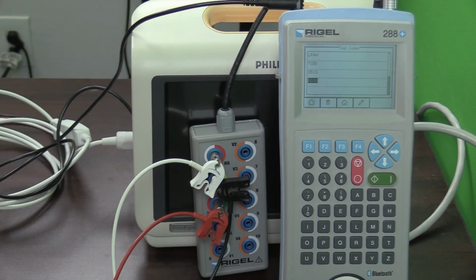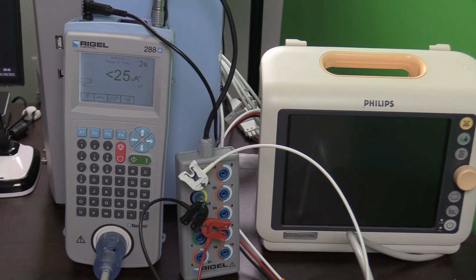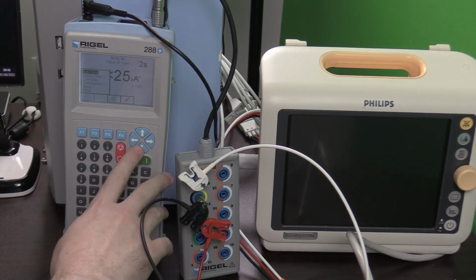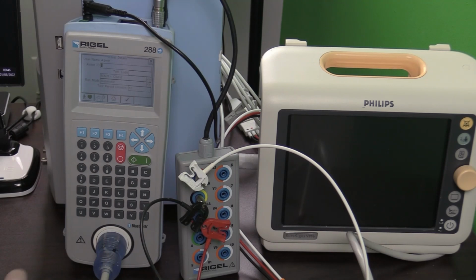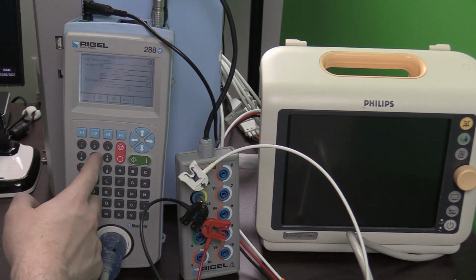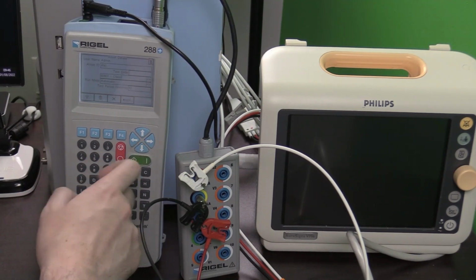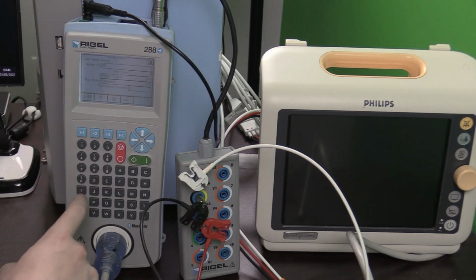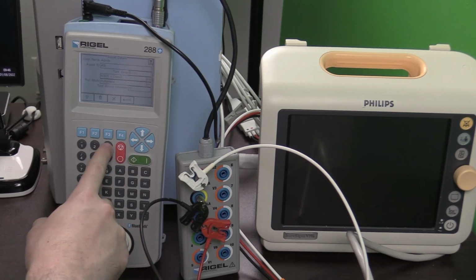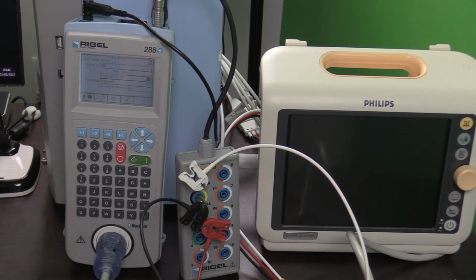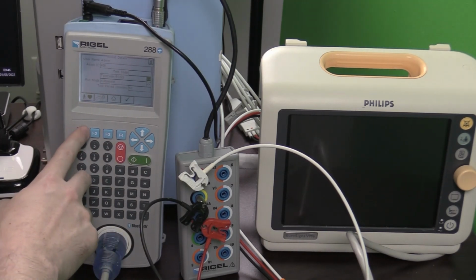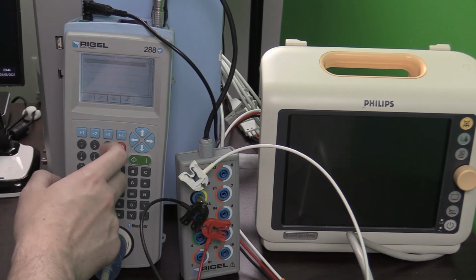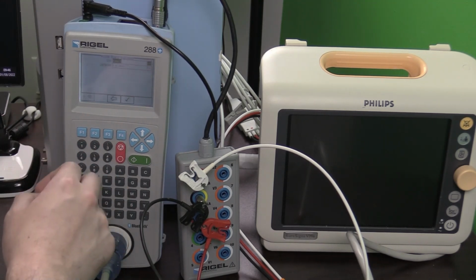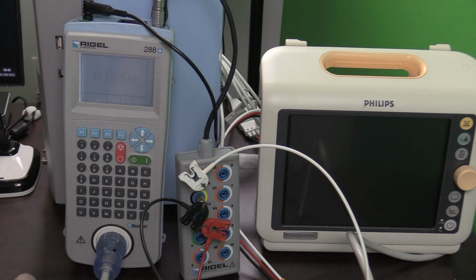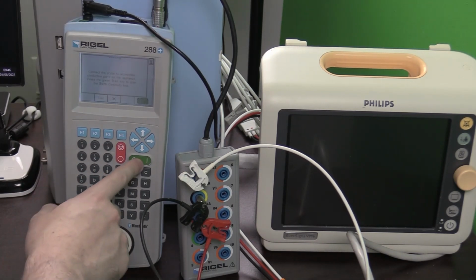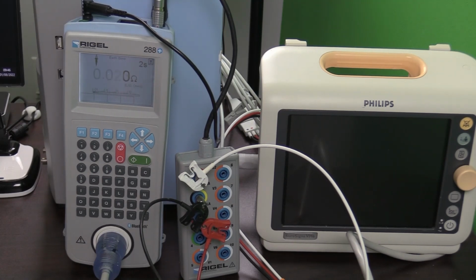Now that we've developed our test code, we can use it in an auto test. So you're going to select F4, auto mode, and your asset ID can be whatever you'd like it to be. I'm just putting in a random number. For test code, we are going to enter that 4-character code that we have already developed, and that will autofill all of the information we've already developed. I'm just double checking here to make sure that it's set up for my 3 ECG lead. Everything is correct. It's giving you the warning of, are you sure you want to run the test? You hit the green button and it starts cycling through the tests.